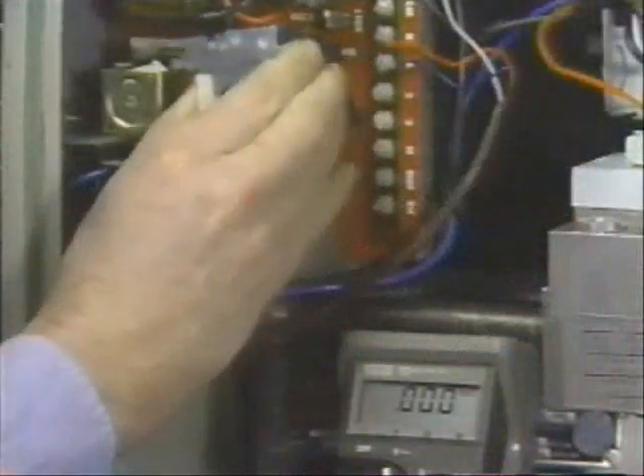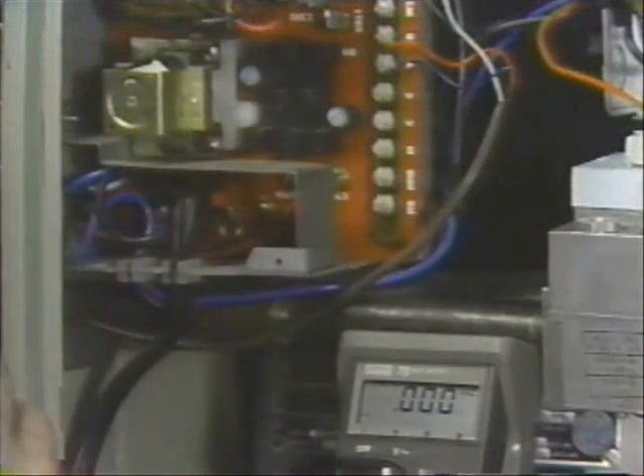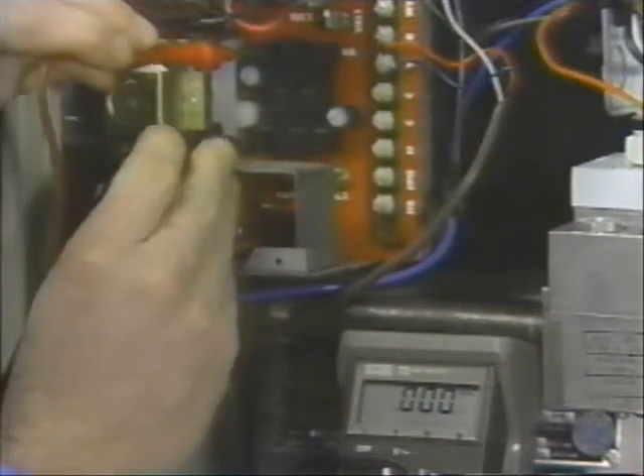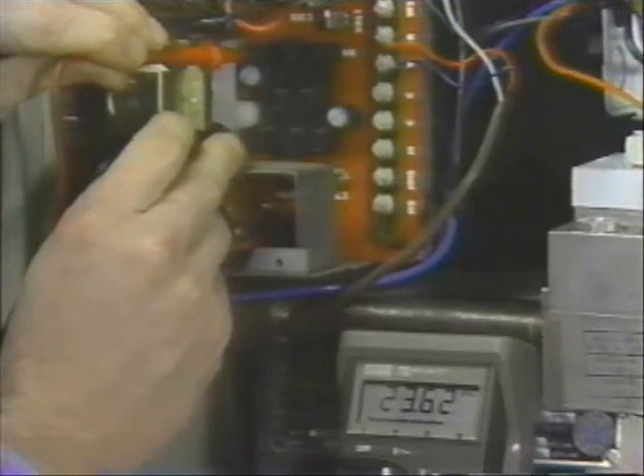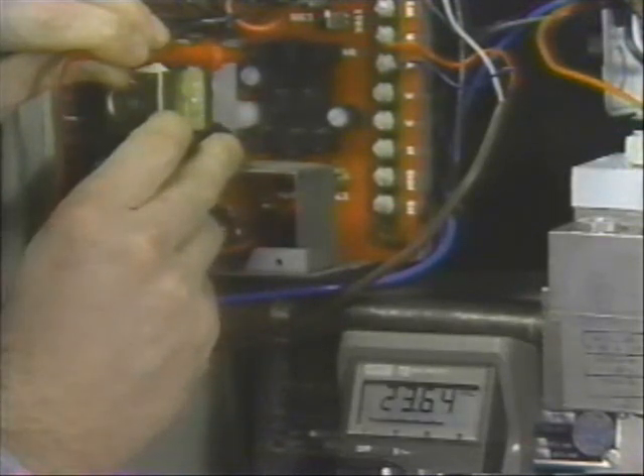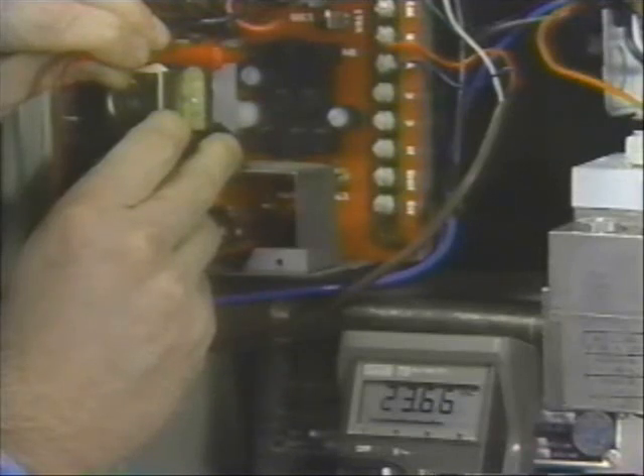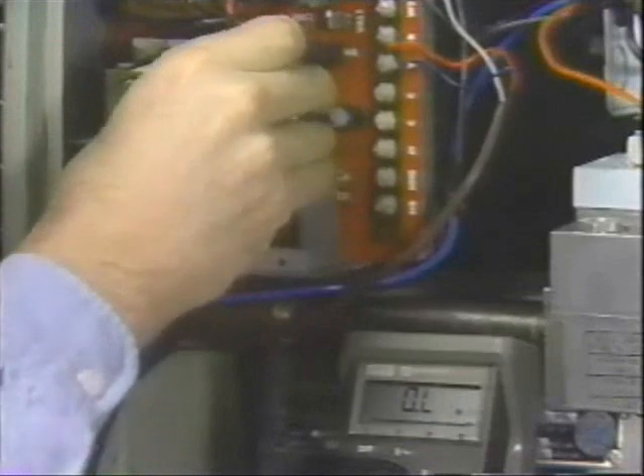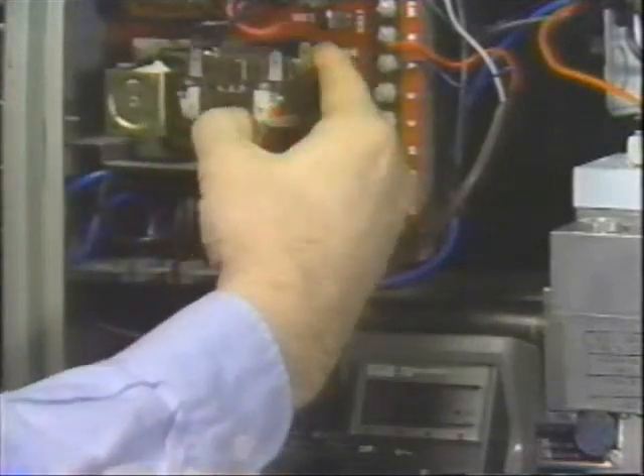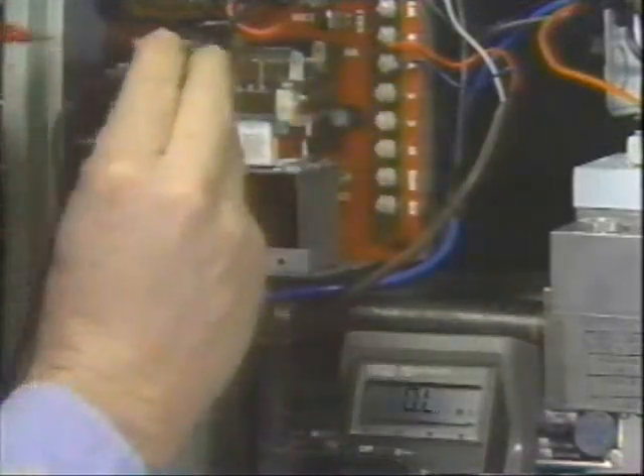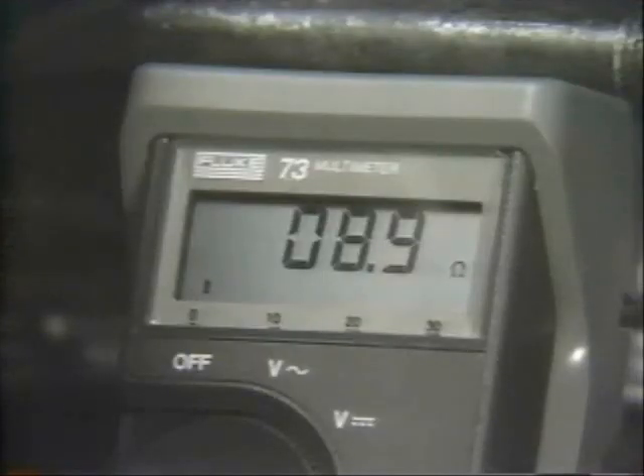Now let's review some general procedures for checking out and servicing relays. When a relay is not operating, the first thing to do is check the coil voltage to make sure it's within 10% of its rated voltage. If that's okay, check coil continuity by measuring the resistance of the coil. When a coil burns out, it usually becomes electrically open, so you'll get infinite resistance. Resistance of about 10 ohms means the coil is okay.